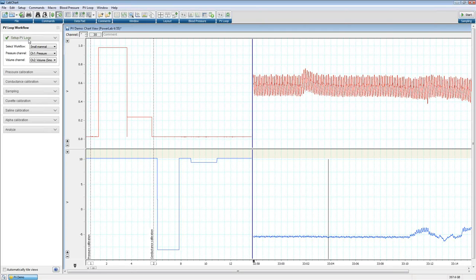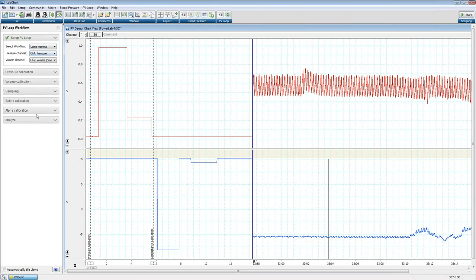With Workflow open, the first thing is how to set up PV Loop in LabChart. You need to select the proper type of workflow — small mammal or large mammal. For small mammals, a cuvette calibration is used; for large mammals, it isn't. The actual MPVS hardware from Millar requires different things. Since this file is from a mouse, we'll use small mammal. We tell LabChart that the pressure channel is on channel 1 and the volume channel is on channel 2, so when we proceed to pressure calibration and conductance sampling, it knows where to look for the proper data.